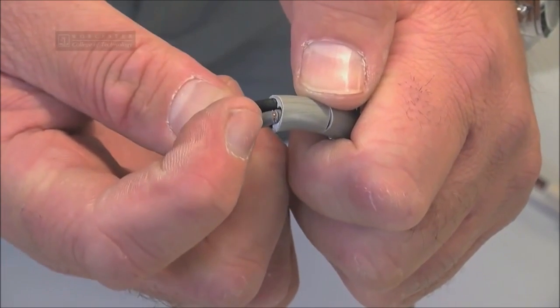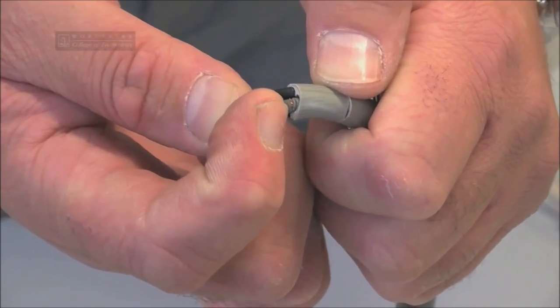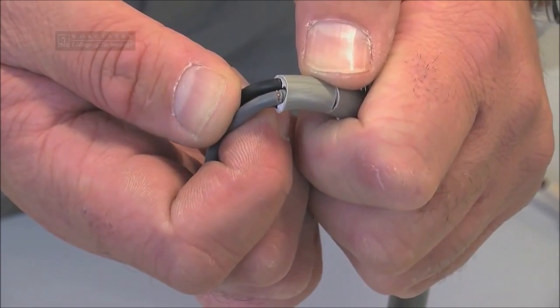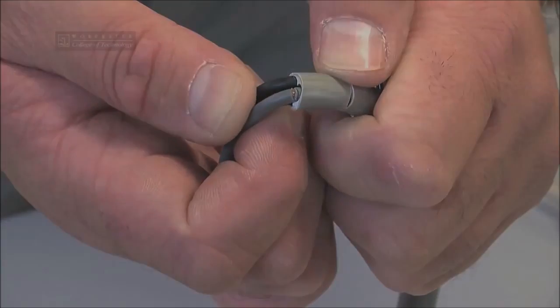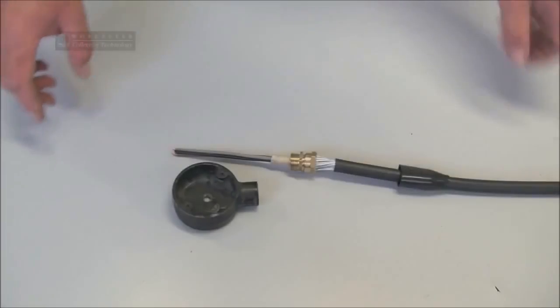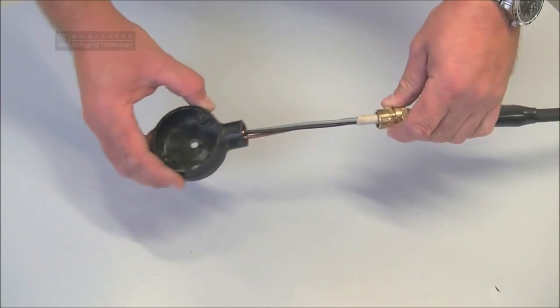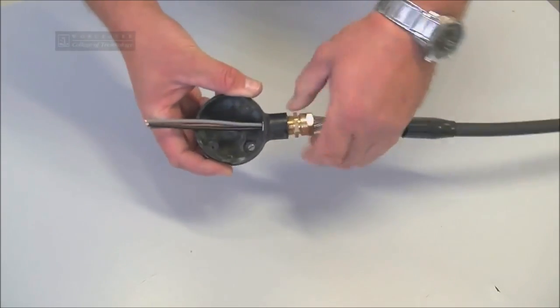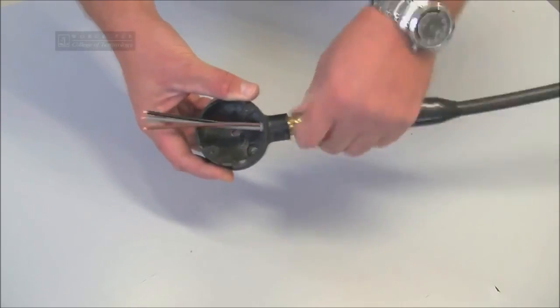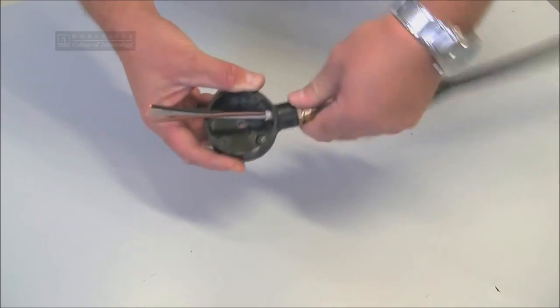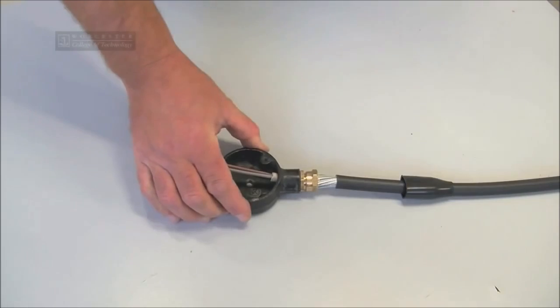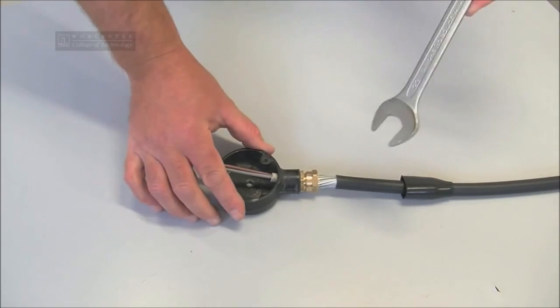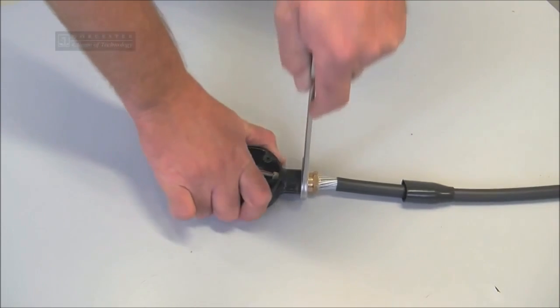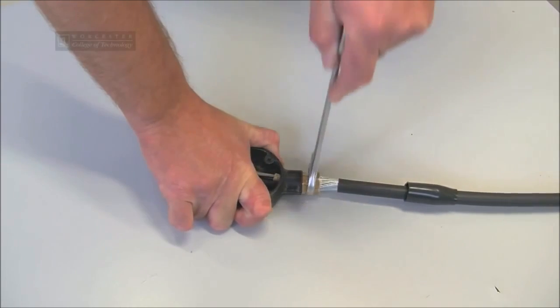As you can see from this example, the knife has gone straight through into one of the conductors. We then introduce the gland into the end box or the terminal box. Nip it with our fingers.